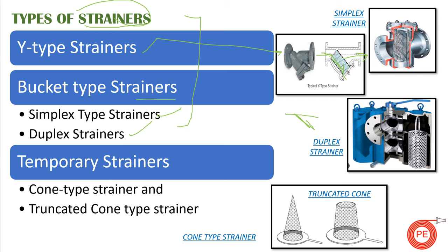The third type is temporary strainers. As the name suggests, these are temporary strainers placed across equipment during commissioning or maintenance phases. Once commissioning or maintenance is over, they are removed, but they are important for saving equipment from solid debris. Temporary strainers include the cone type strainer, which looks like a cone, and the truncated cone type strainer. These are used across industry depending on requirements, placed before equipment to meet operational needs.